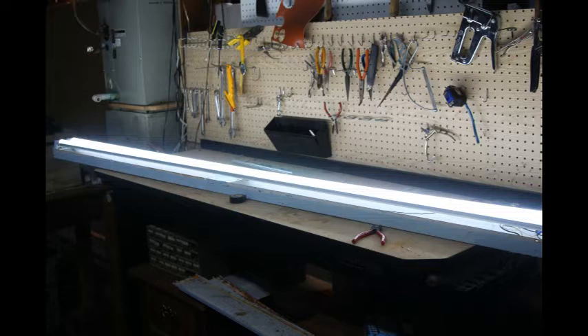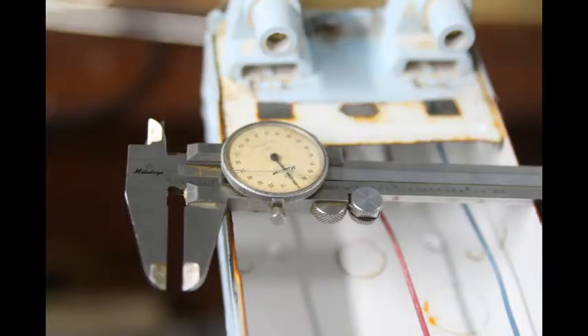These tubes that I just put in are rated at 36 watts, and they produce as much or more than the 75 watt fluorescents that they replaced. Quite a bit of that is the energy that was used to produce the heat in the ballasts.